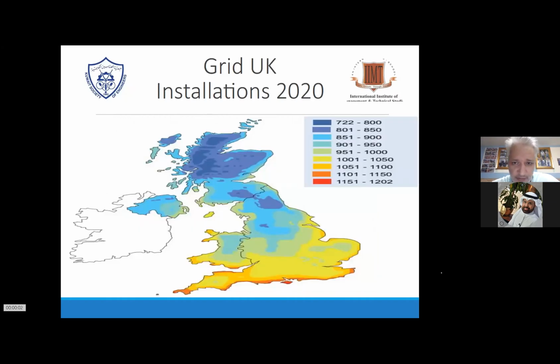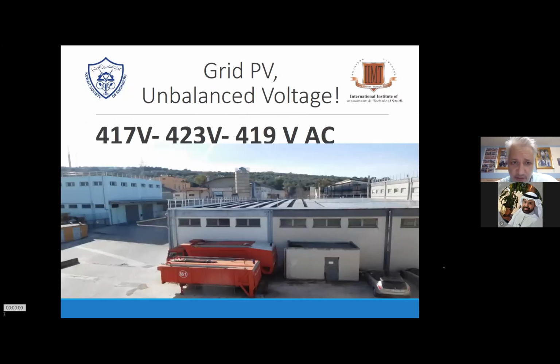There will be some interesting graphs in UK. I did lots of commissioning and installing in 2012 to 2018, and later on only commissioning and troubleshooting. You can see at the bottom, this is in line with Nice, France. So they have also 1150 to 1200 watt in Poole, Southampton, for example. That's the plant in Italy, in Sardinia. You can see the different variations: 417, 423, 419. So the inverters which are installed at the house on the right side have to feed now with 4 or 5 volt more, to overcome the burden of the already existing.